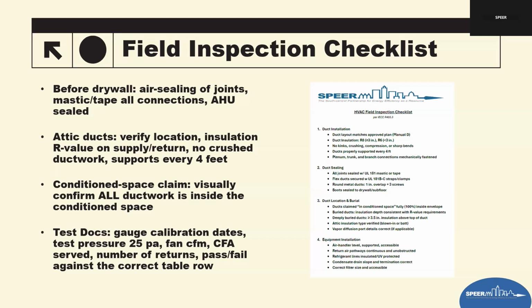Conditioned space claims. If the contractor is saying the ducts are all in conditioned space, as we talked about earlier, are they all in conditioned space? It must be on the conditioned side of the insulated thermal envelope. Period. It should not be pushed against outer air barriers. It should not be pushed against decking board and then foamed around it. That is now considered outside of conditioned space. So to claim it's fully in conditioned space, we must verify that it is not in contact with the thermal envelope or the outermost air barrier. Any section that's left in the attic, the garage, the vented crawl space, any place like that, can invalidate the claim if it is not fully inside the conditioned side of the thermal envelope.